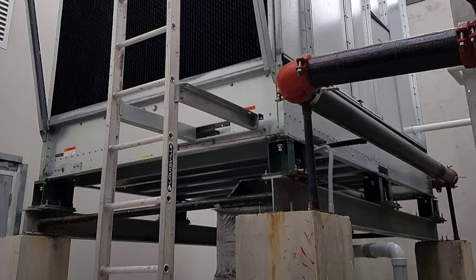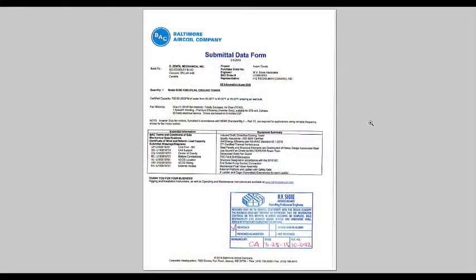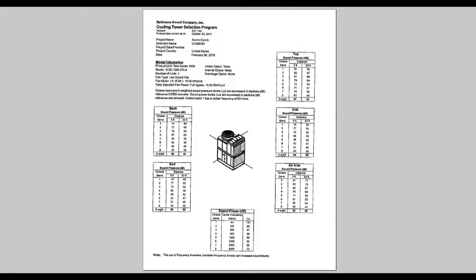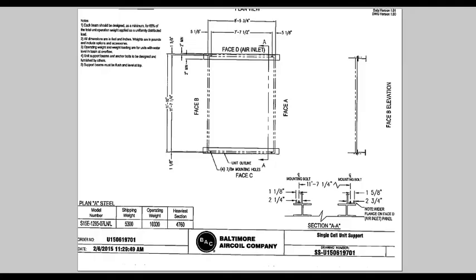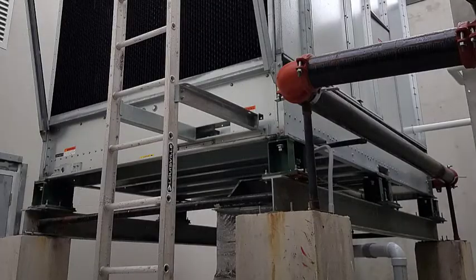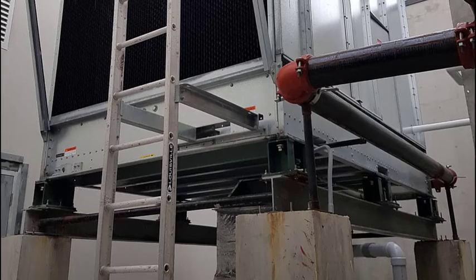this. When I checked the cooling tower submittal, which had been reviewed and approved by the mechanical engineer of record, the manufacturer showed the need for beam supports on the two short sides of the tower. So hopefully the contractor didn't just assume it would be okay, and either the tower was already able to be supported at the 6 points, but the submittal didn't show it, or the manufacturer made a change to allow this. Otherwise, it is very possible that the tower casing could have failed when filled with water.